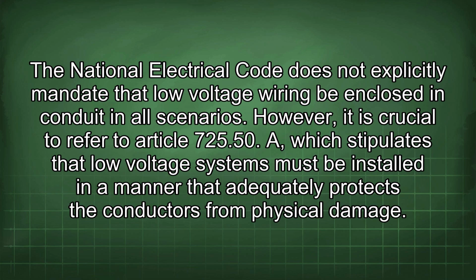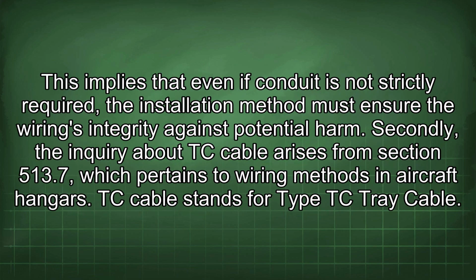However, it is crucial to refer to Article 725.50(A), which stipulates that low-voltage systems must be installed in a manner that adequately protects the conductors from physical damage. This implies that even if conduit is not strictly required, the installation method must ensure the wiring's integrity against potential harm. Secondly, the inquiry about TC cable arises from Section 513.7, which pertains to wiring methods in aircraft hangars.